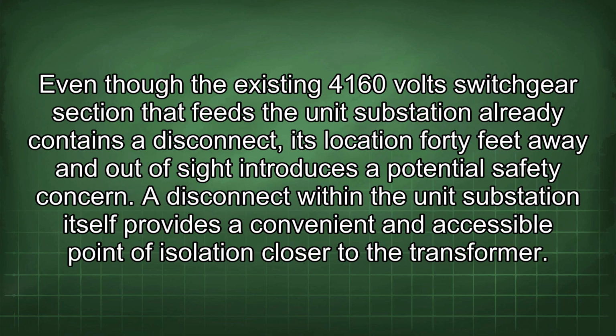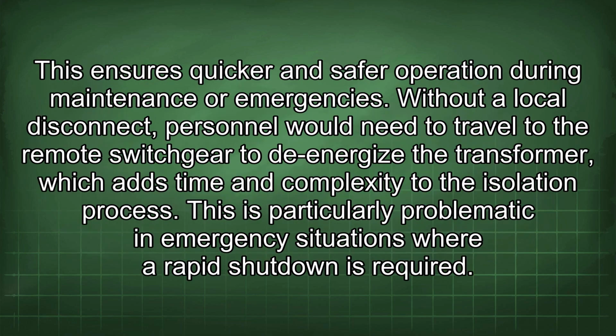Even though the existing 4160-volt switchgear section that feeds the unit substation already contains a disconnect, its location 40 feet away and out of sight introduces a potential safety concern. A disconnect within the unit substation itself provides a convenient and accessible point of isolation closer to the transformer. This ensures quicker and safer operation during maintenance or emergencies.